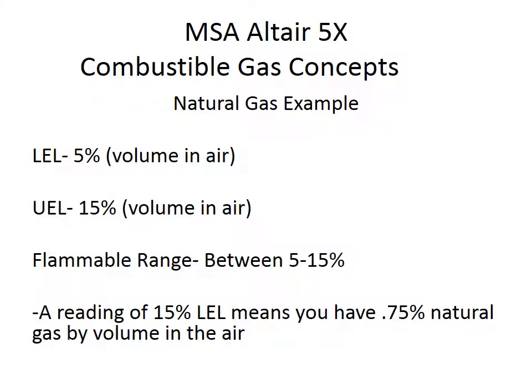Some other combustible gas concepts, just using an example. The LEL for natural gas or methane by volume in air is 5%, and the upper explosive limit is 15% volume in air. So you can see that the flammable range is between 5 and 15%. So a reading of 15% LEL, what does that mean? Well, it means you have 0.75% natural gas by volume in air. Remember, you need to get to that 5% volume in air of natural gas to hit that lower explosive limit. So at 0.75%, 15% of the LEL, you're too lean to burn, okay?